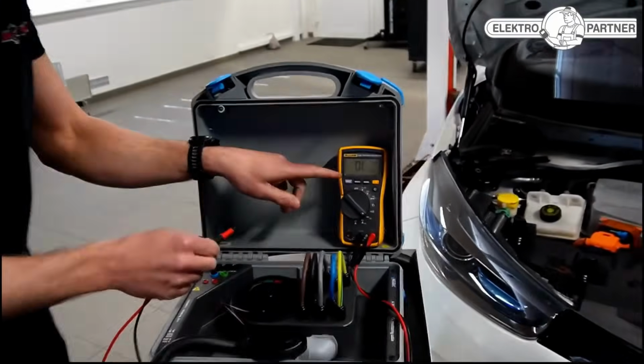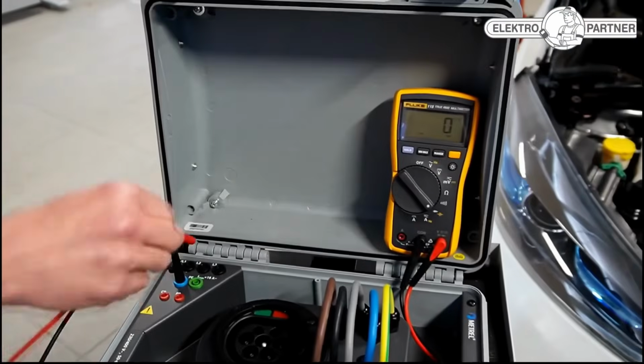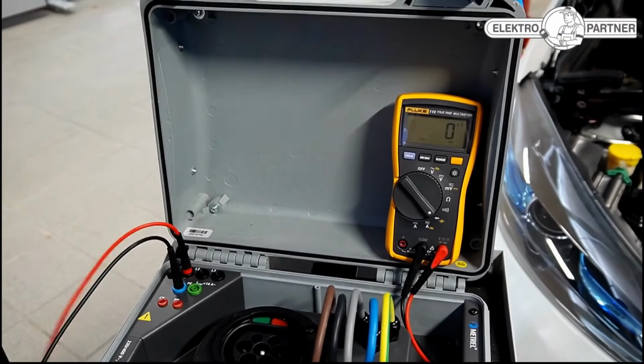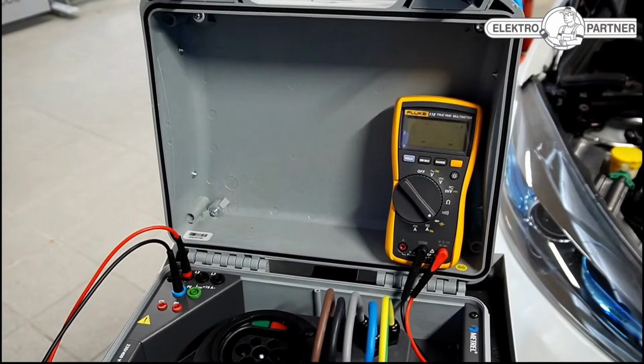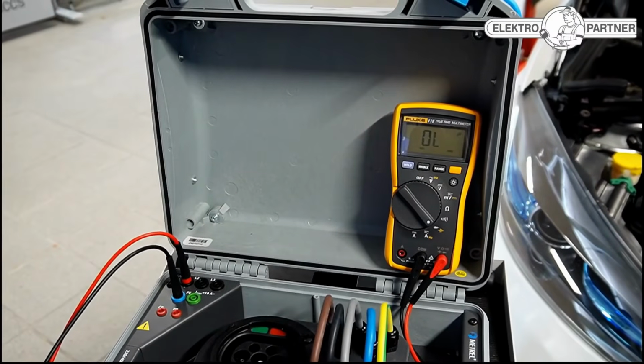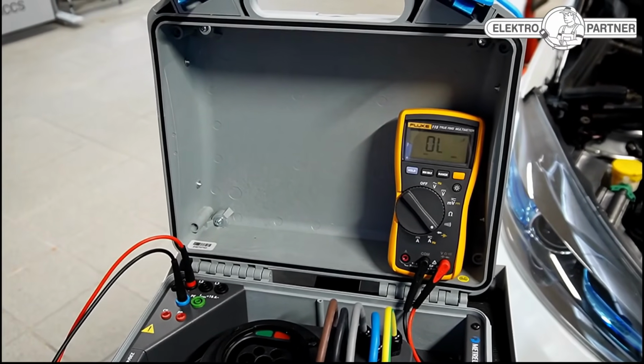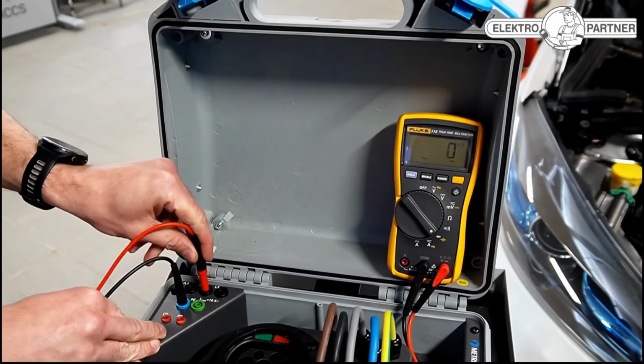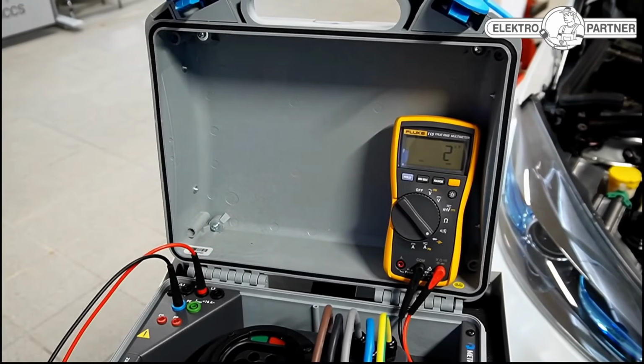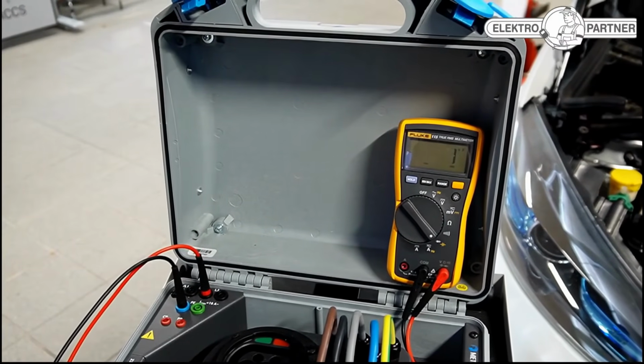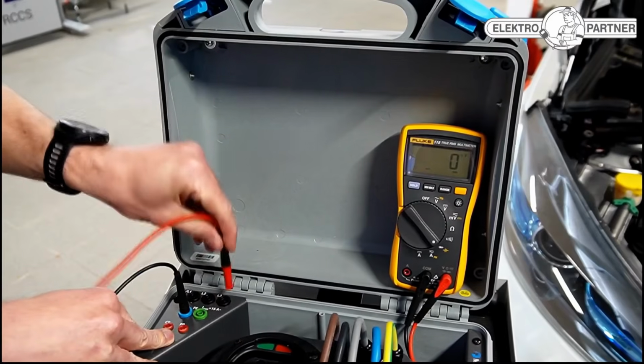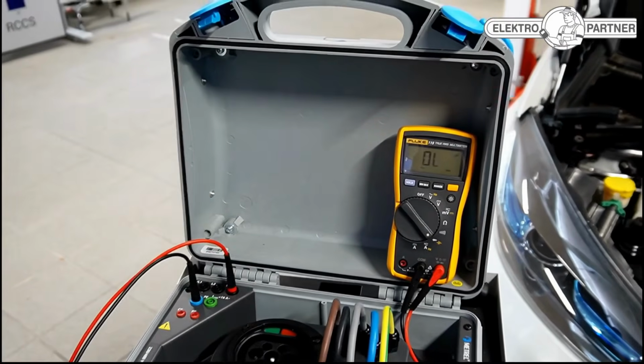So we've connected our multimeter and we're testing the capacitors, and we've now connected phase 1 to ground. This is where we're supposed to measure the 115 microfarads. We're trying to check in relation to phase 2 - still absolutely nothing. And now in relation to the upcoming phase 3.